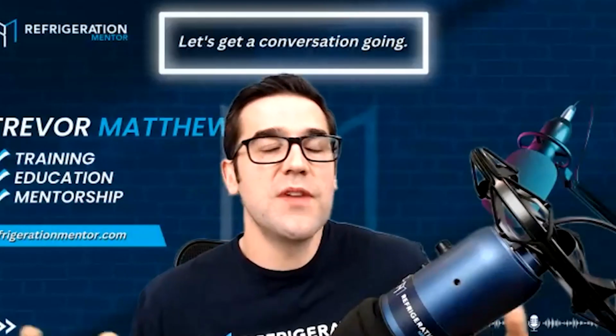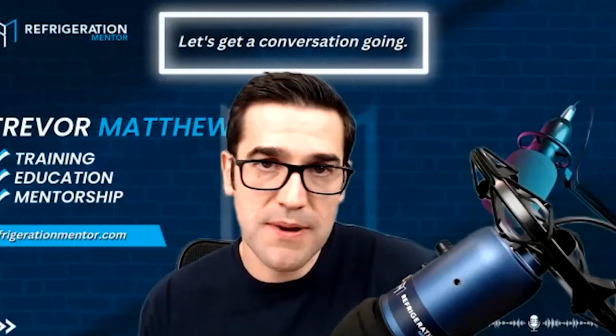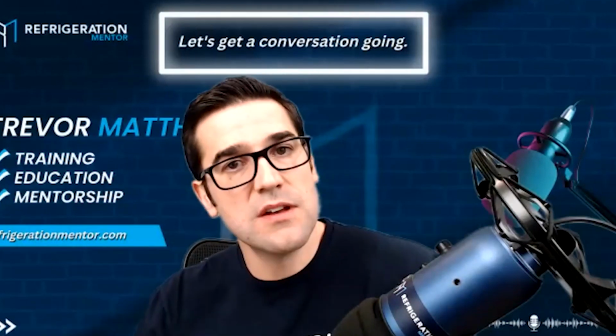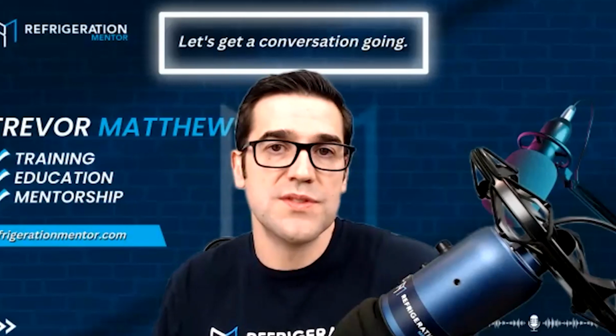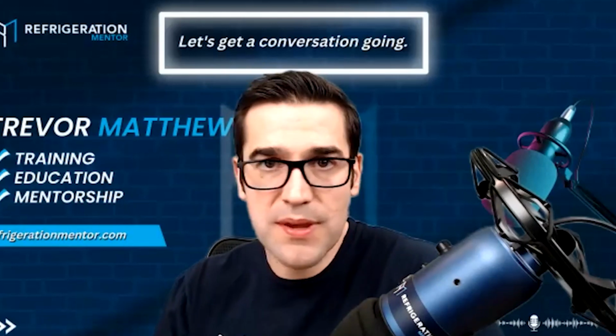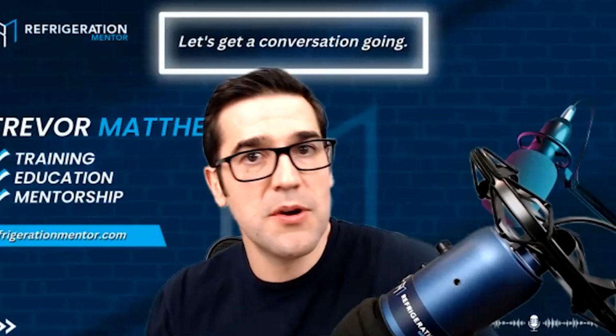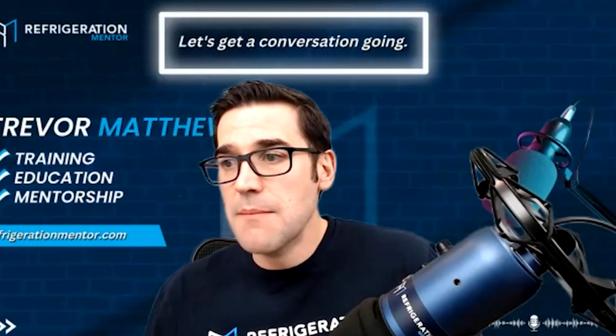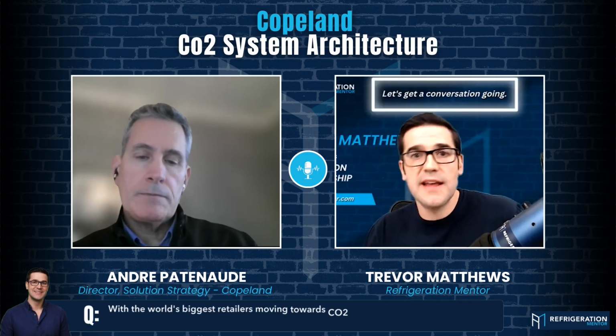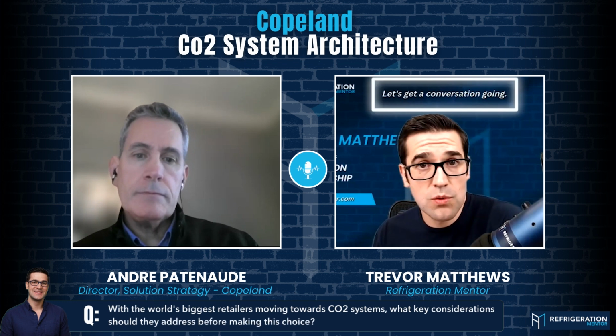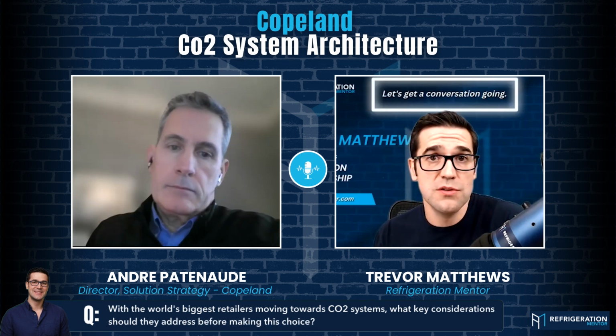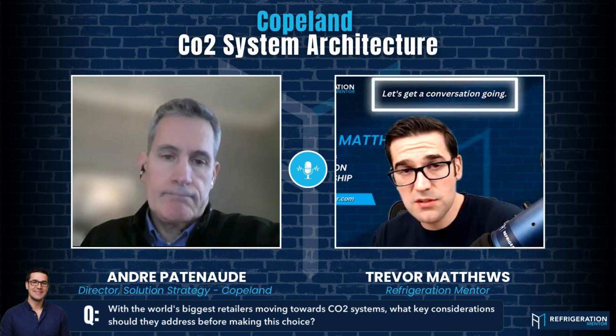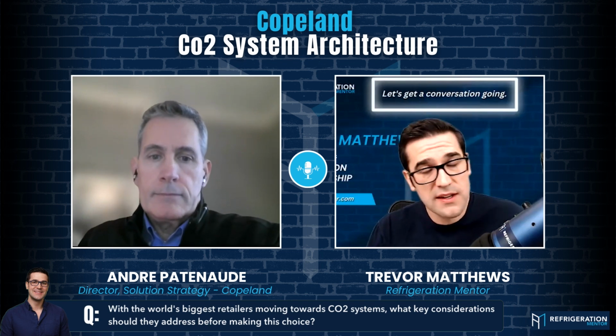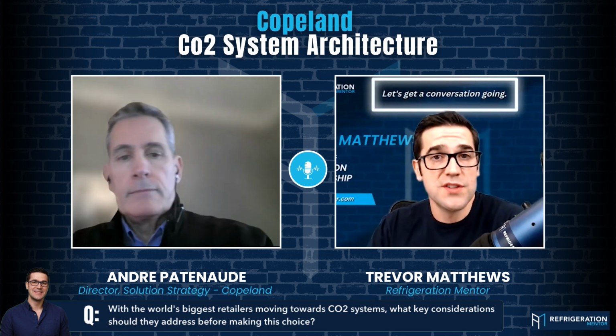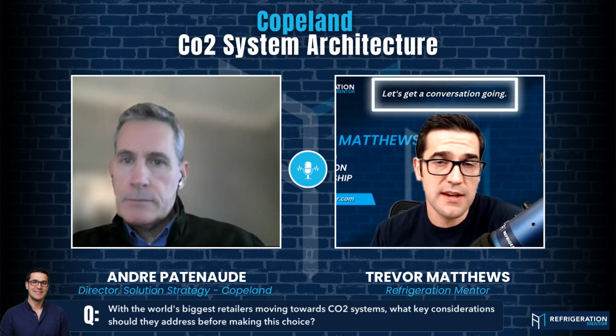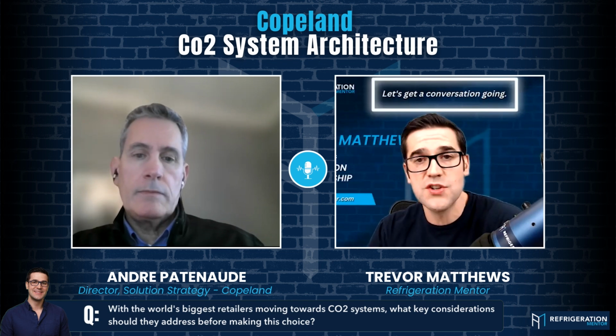Like we've talked about before, the transition has been happening: low GWP, phase out of high GWP refrigerants. We're seeing things like PFAS and TFA being discussed in Europe for F-gas. But we know it's been happening—the biggest retailers in the world are starting to say we're going to go CO2, whether it's transcritical, subcritical, secondary, whatever. We know they're starting to make that move.